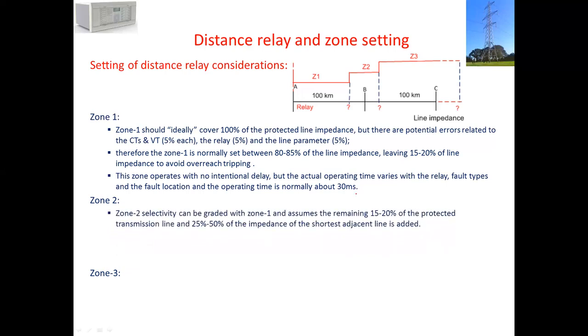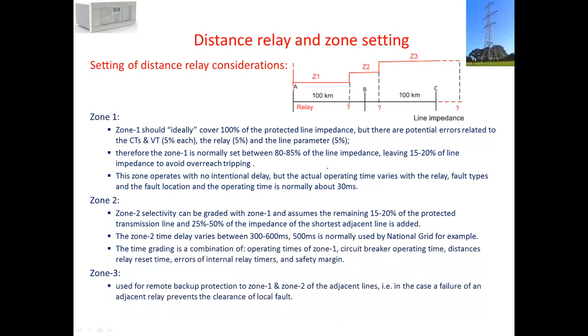Zone 2 protects 100% of line A to B plus around 25% to 50% of the next line. The time gradient is a combination of zone 1 plus circuit breaker opening time, distance relay reset time, error of the internal relay timer, and safety margin. This all adds up to around 500 milliseconds, between 400 to 600 milliseconds. 500 milliseconds is normally used.